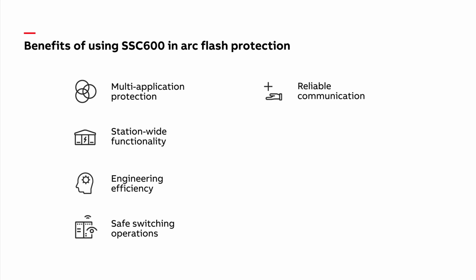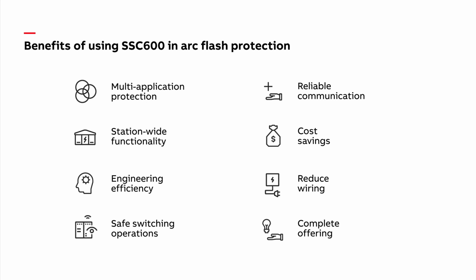Reliability. SSC600 supports redundant communication with PRP, Parallel Redundancy Protocol, which increases the reliability of communication in the complete arc protection system. Time and cost savings. Less wiring inside the switchgear and fewer engineering hours. Complete offering. ABB can offer complete arc protection systems including arc-resistant switchgear, light-sensing merging units, and even ultra-fast earthing switches. These can be offered as fully engineered turnkey solutions.